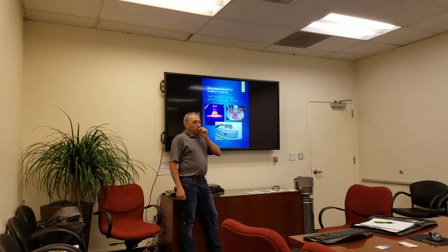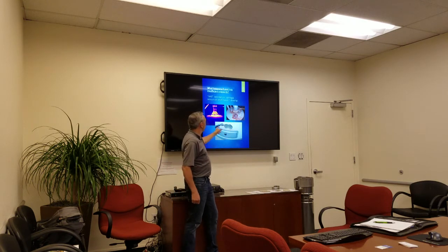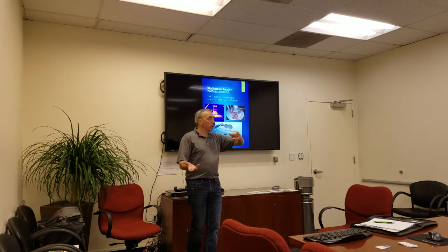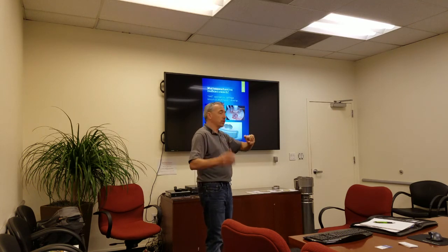I mentioned blowing smoke into the stack. You could do that here. If the chimney was at a negative, it would suck the smoke up the stack. If not, it would just hover around the room. And here's a mirror. Some techs will use a mirror. If it fogs up because of all the moisture in the flue products, the mirror will fog up if it's not venting properly.